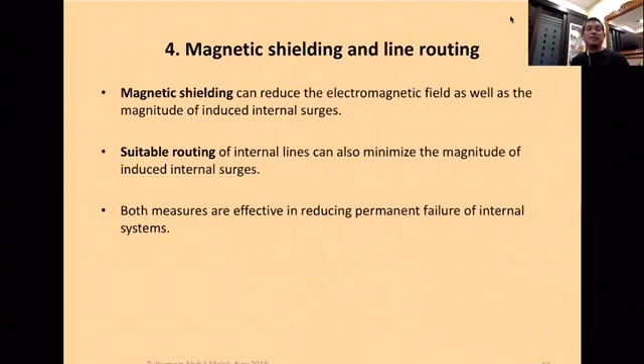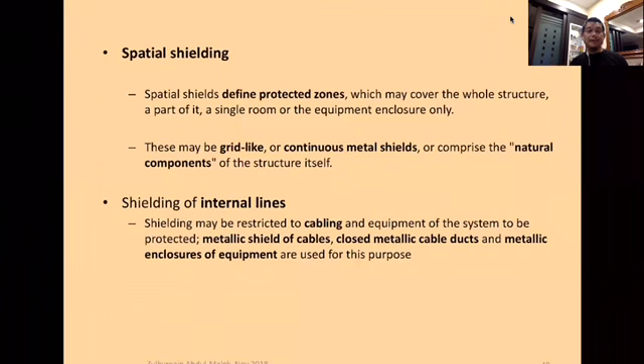Now, magnetic shielding and line routing. If we have shielding, we need to construct the shield properly, or we can use line routing technique. Line routing is actually to minimize the loop electromagnetic interaction. So either we use spatial shielding by special walls or grid-like structures, or we can use shielding of our lines by line routing or by shielded lines or conduits to make sure there is no coupling for the lines inside the structures.